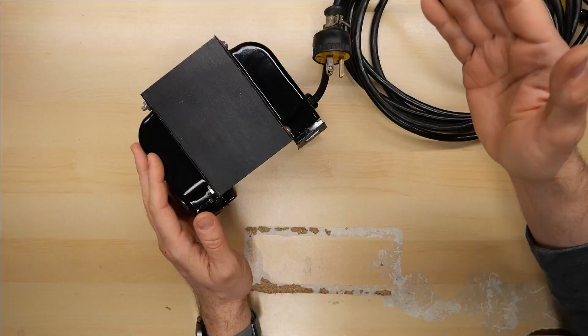The benefit is all about safety. If I plug a lamp into here and grab the live or hot wire on the secondary side, say there's an exposed wire and I touch it, I'm not going to get a shock if my other hand is touching something else in the house referenced to the house power. Normally touching the ground or neutral on an outlet cover would give you a shock - I have ground fault interrupt outlets down here in the basement so it would shut off the power, but I could get shocked if those weren't working or I didn't have them.